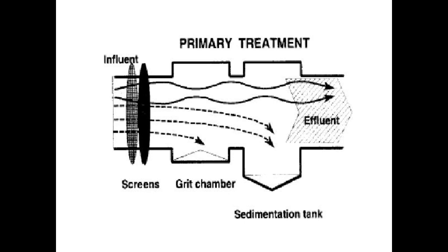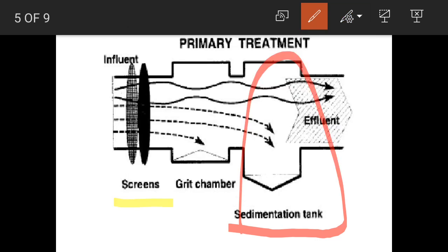Let's discuss the diagram of primary treatment. Primary treatment is used for the removal of fine suspended organic solids that cannot be removed through preliminary treatment. So fine organic solids are removed through primary treatment in the sedimentation tank. The screens and grit chamber are part of preliminary treatment, and water enters from preliminary treatment into the sedimentation tank.